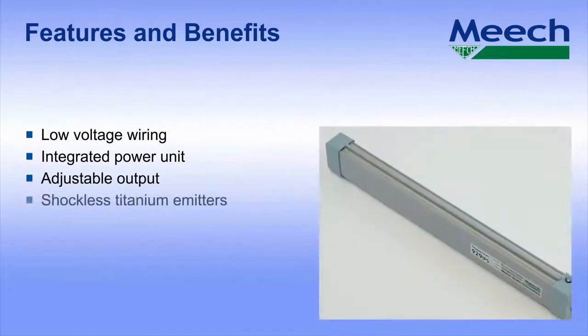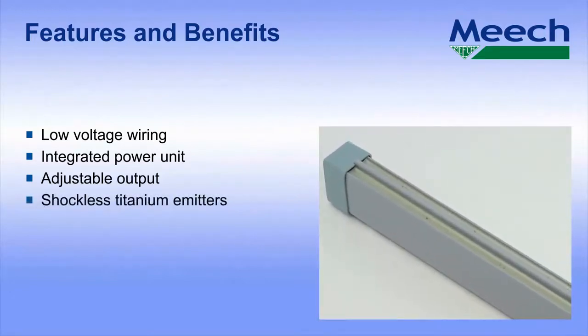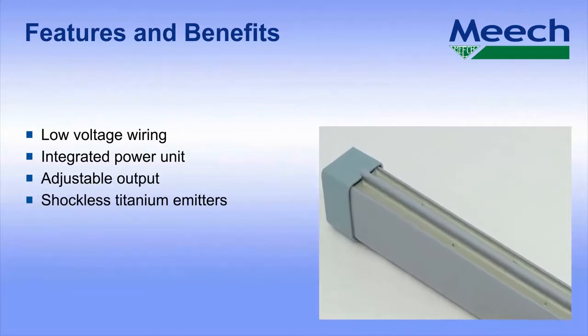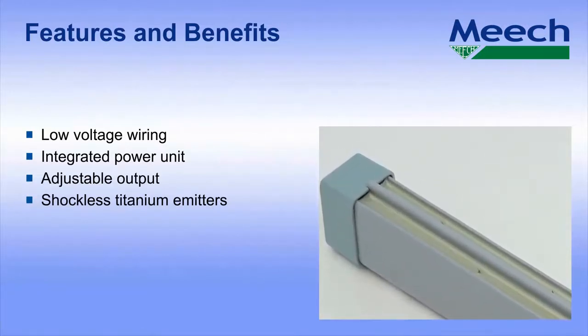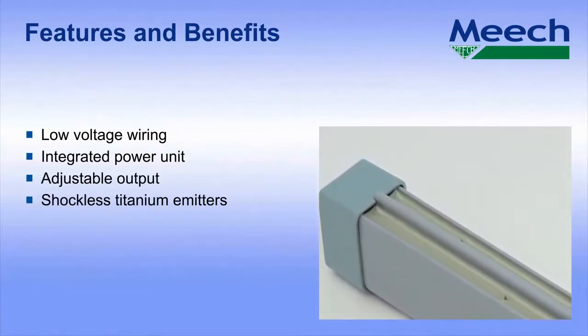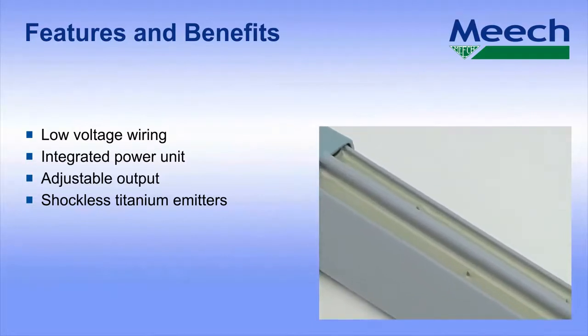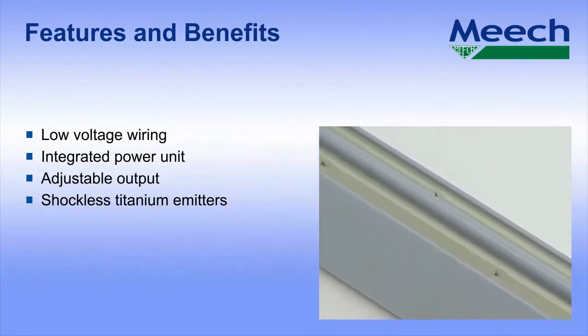Shockless titanium emitters. The titanium emitter pins on the 929 IPS are resistively coupled to the high voltage supply. Independent research has shown that titanium is one of the very best materials for emitter pins, with extremely low wear rates.